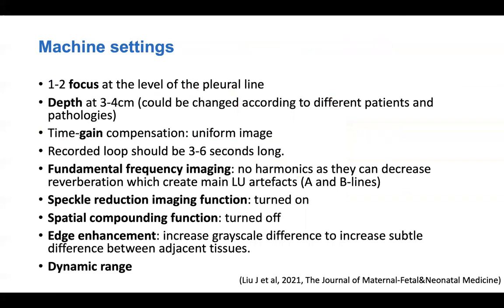To summarize the recommended machine settings for lung ultrasound in the neonate, following the recent recommendation published here in 2021, we should use 1 to 2 focus at the level of the pleural line, adjust the depth at 3 to 4 centimeters, and this could be changed according to the different patients and pathologies, optimize time gain compensation to obtain a uniform image, record loops only, not images, for a duration of 3 to 6 seconds, and mainly remove harmonics, as they can decrease visualization of the pleural line and main lung ultrasound artifacts.